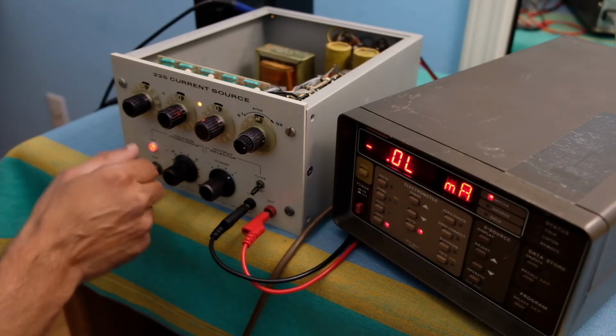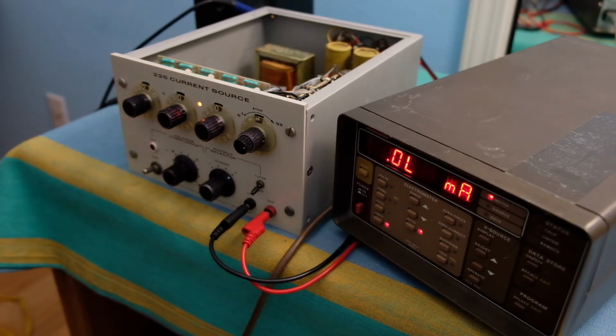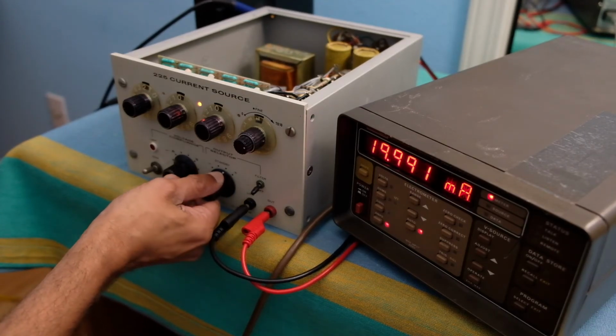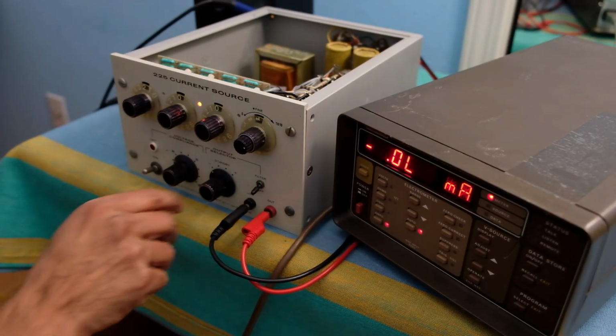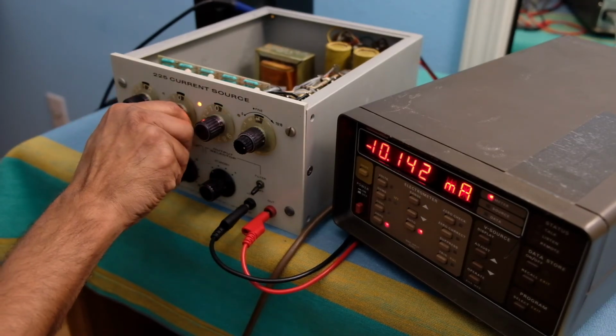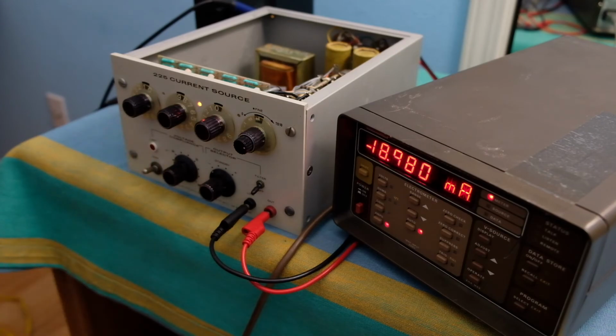And let's go to the highest range, and that's going to be, okay, I've overloaded this machine. Looks like, I think it's 20 milliamps maximum, I'm not sure. 19.993. Okay, it's exceeded 20 milliamps. So I think that's the limit on this one. -19. It's not bad. 18.99. So yeah, I think this is pretty good at this point. I don't know how to adjust this without doing some more detailed resistance measurements to see the different scales, some issues somewhere, but at this point this is a very usable machine.